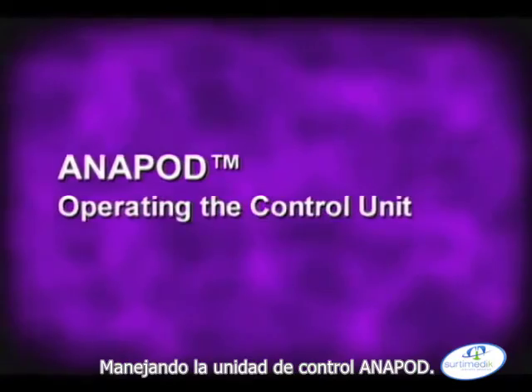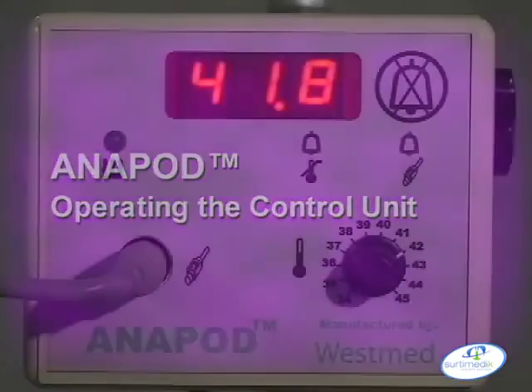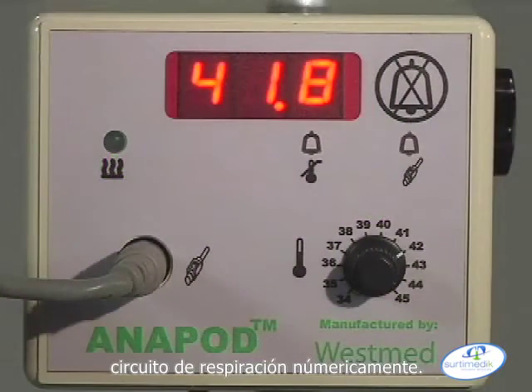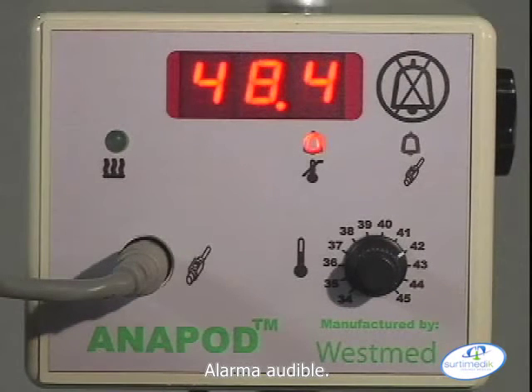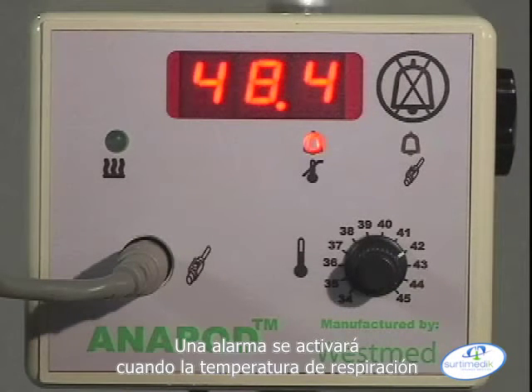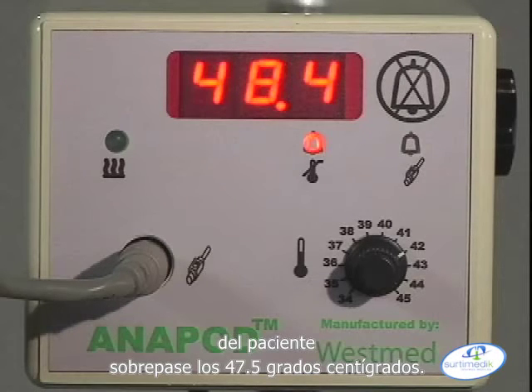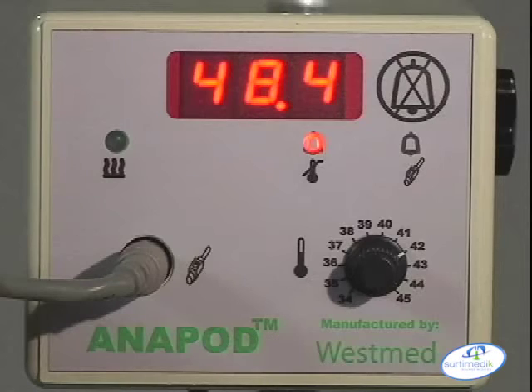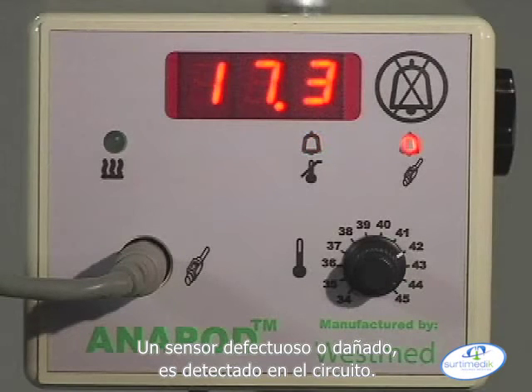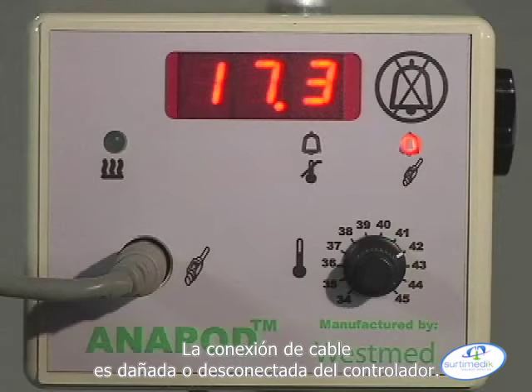Operating the Anapod control unit. Temperature display illustrates breathing circuit temperature numerically. Audible alarm. An alarm will activate when patient breathing circuit temperature exceeds 47.5 degrees centigrade, a defective or damaged sensor is detected in the wick circuit, or the cable assembly is damaged or disconnected from the controller.